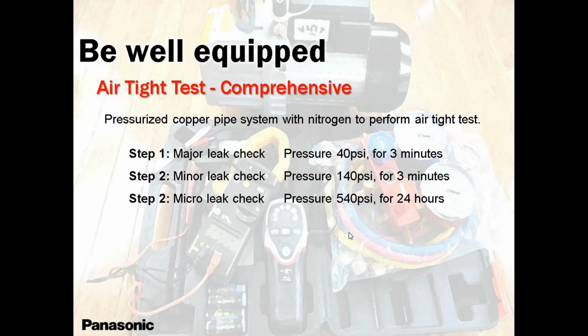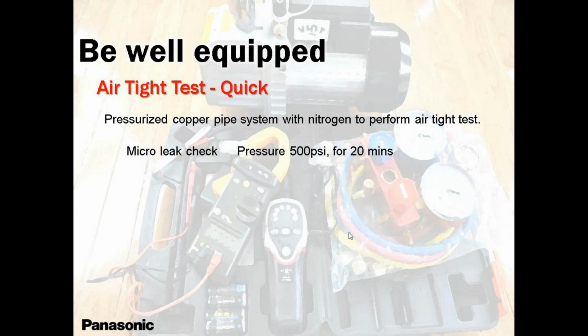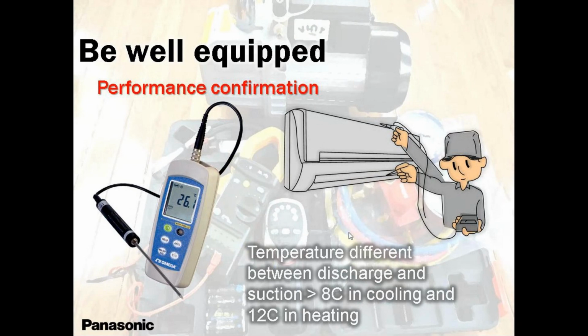This is another slide showing you an example of leak, dust, and moisture in the system. So again, nitrogen and deep vacuum will always clear all these issues. Use proper gauges. Don't mix gauges. You know how to do that. Don't mix gauges of 410 with 22. If at all you have 22 still in the market, or 410 with another type of gas.